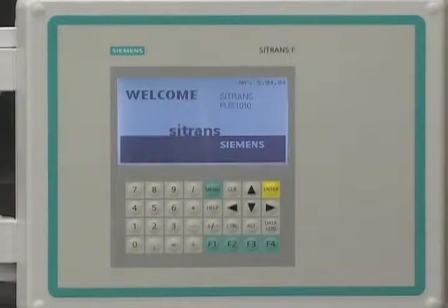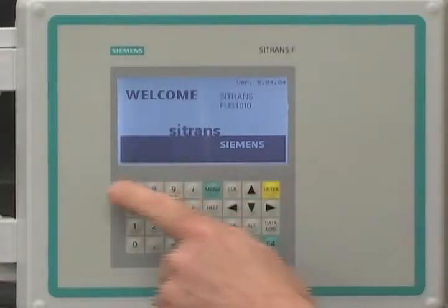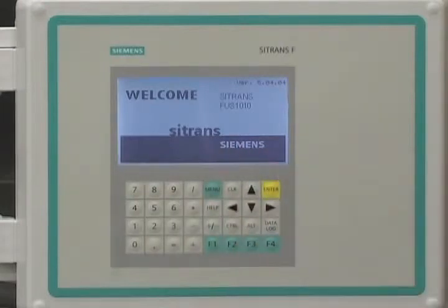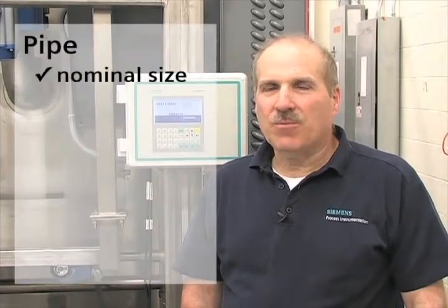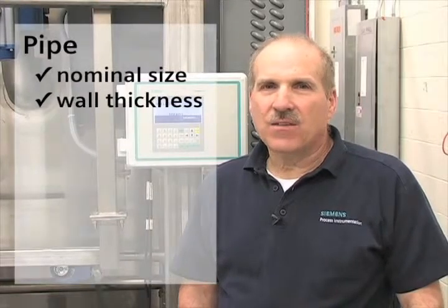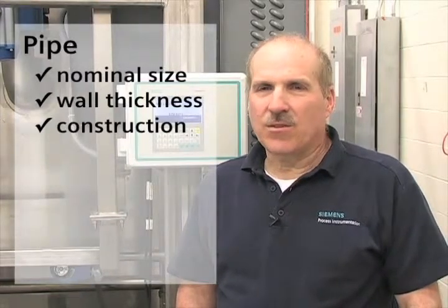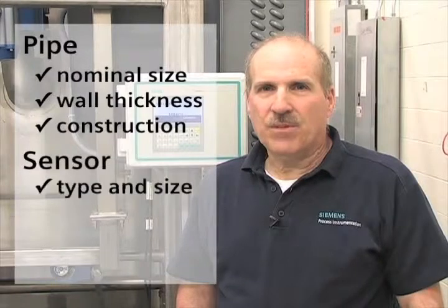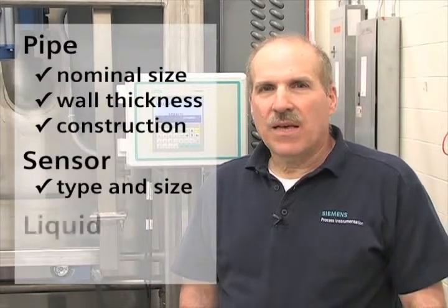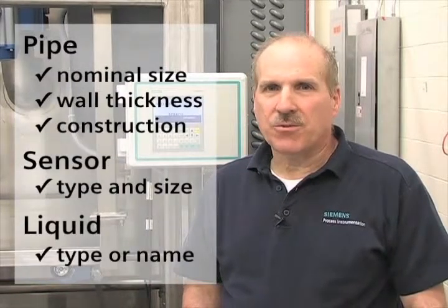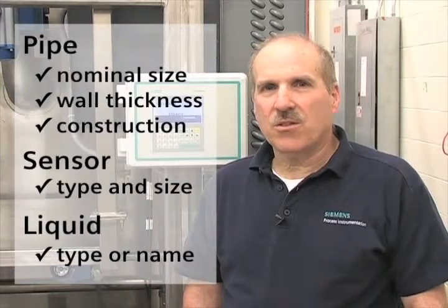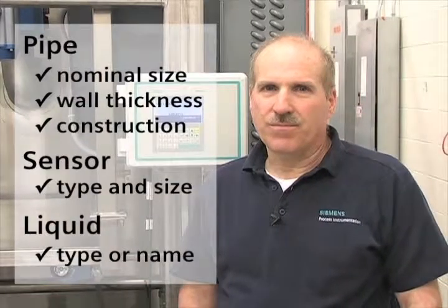The SITRANS FUS1010 keypad, graphical display, and menu-driven software make configuration simple. To configure the SITRANS FUS1010, we need the following application details: the nominal pipe size, wall thickness, and construction material at the sensor location, the type and size of sensor being used, and the type of liquid we will be measuring. Our first step is to create a site name for our application.